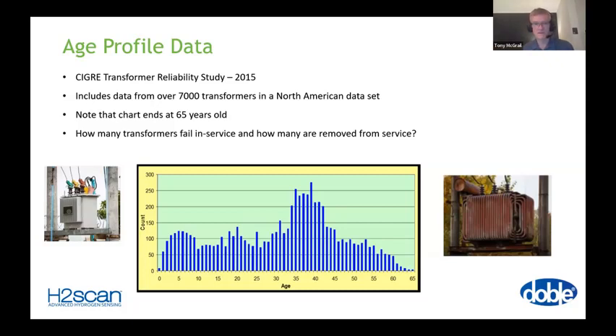External rust, as you might see on the right-hand side, is definitely not a good thing, but it's far better than internal rust, which we sometimes see on transformers. And one of the questions I sometimes ask is, if I have a transformer which is 1 year old, looks a bit like the one on the left in the picture, and I have one which is 50 years old, looks a bit like the one on the right, and when I do a full assessment, they're in the same condition, if I had to choose one, which would I keep? And I would always say, choose the 50-year-old one, because it's only going to get worse over another 50 years, whereas the first one is going to deteriorate over one more year. So after 1 year, it's lost a certain amount of its capability, whereas the other one took 50 years to get to the same point.